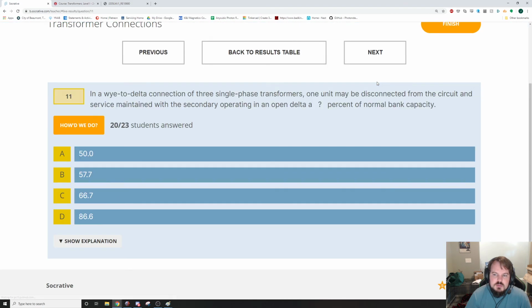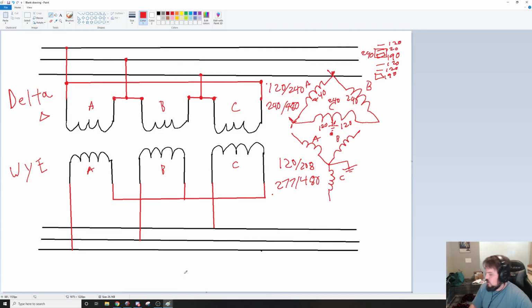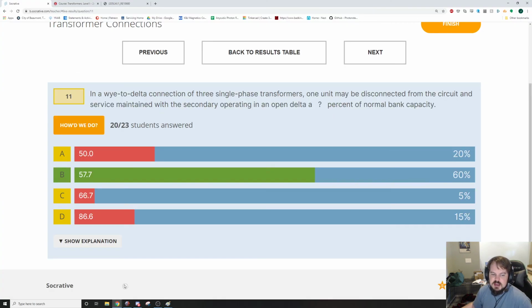Alright. In a Y to delta connection of three single-phase transformers, one unit may be disconnected from the circuit. Okay, so in this instance, this would be you disconnecting one transformer, or clearing it out, getting rid of one of the transformers. And then you have what they call an open delta. And the open delta still can do all the things a regular transformer can do, just at 57% of its capacity. But it lets you keep the building running while you do repairs on one of the transformers.